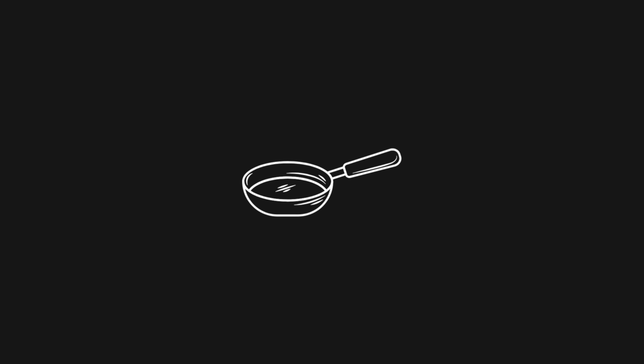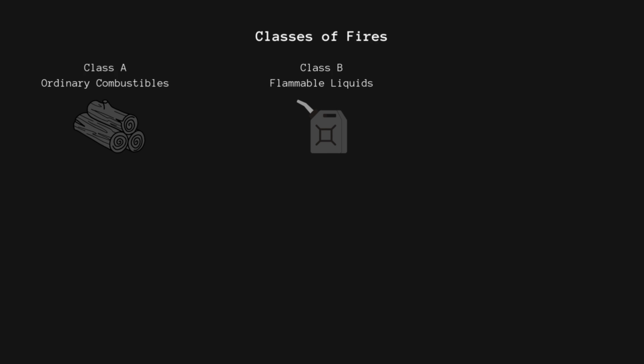First is Class A fires, involving ordinary combustible materials such as wood, paper, cloth, and various plastics. To put them out, you should use either water or an ABC extinguisher. These are the most frequent types of fires in residential and office environments. Class B fires involve flammable liquids like gas or oil and require CO2, dry chemical or foam extinguishers to smother the flames without using water.